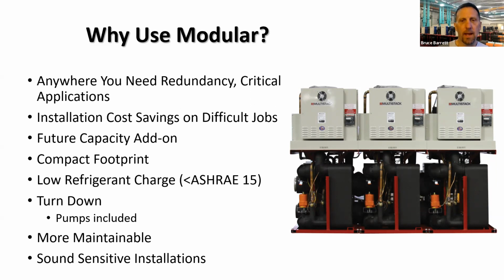Maintainable. By that I mean, if you lose a component, you don't lose the entirety of your chiller. So redundancy, N+1, 2N, becomes much more footprint and cost conscious with the modular concept. And we've done a number of sound sensitive installations. We've replaced chillers in mechanical rooms, applied our acoustic panels to them, and allowed the facility to actually use space next to the mechanical room versus blanking that out because it was simply too loud to work.